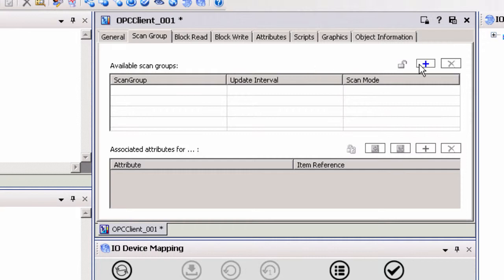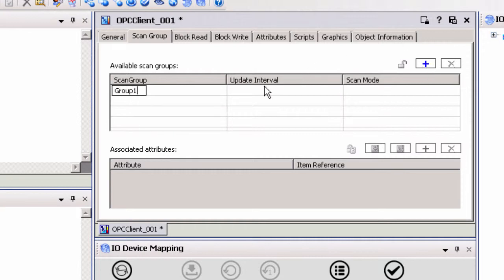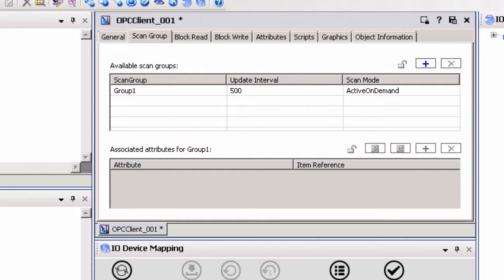To add a new scan group, click the add icon next to available scan groups. This will allow you to give your scan group a meaningful name and define the rate at which System Platform will request updates for the items in this scan group. With a scan group configured, there are three options for adding items to a group: add the item reference manually, browse the OPC server tag database, or import a CSV file with the tag information.